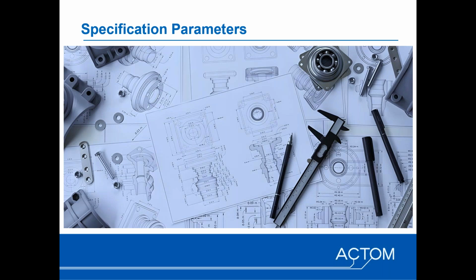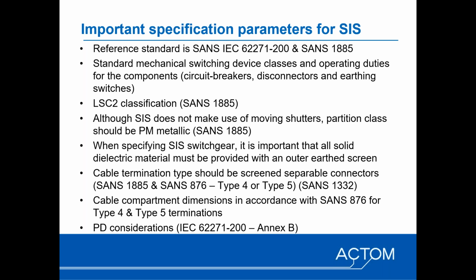The other aspect we mentioned, and hopefully some of the issues have become clear, was what to be aware of if you are going to consider purchasing solid dielectric switchgear or even specifying it. So first of all, it's covered by the standards effectively. We've talked about all the concepts applicable to -200, and all those same principles and concepts apply to solid dielectric insulated switchgear, which is housed within a metal enclosed assembly. So the reference standards are the same: IEC 62271-200, which has been adopted as a SANS standard without any deviations. And then the front end, SANS 1885, which was previously NRS 003, which provides preferred requirements for users within South Africa, noting specific South African conditions and industry norms.